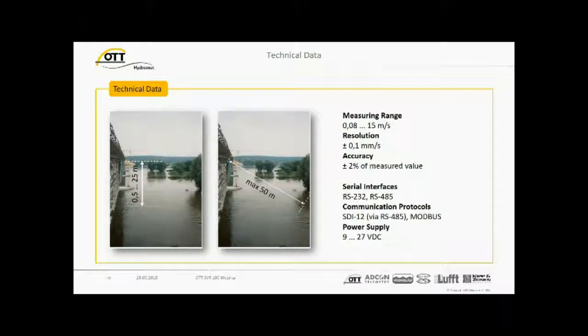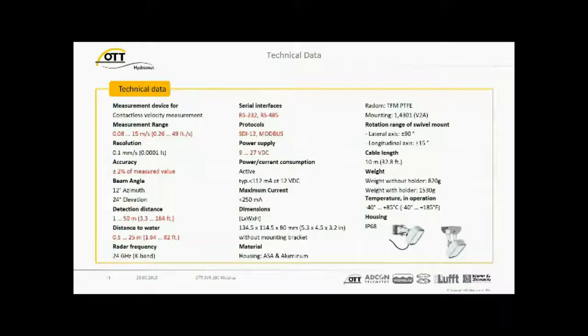If we power the instrument, it is powered on, and then it's continuously operating. You can send SDI commands via RS-485 and request data and change parameters, but it is not a physical SDI-12 interface where you have the power supply included.